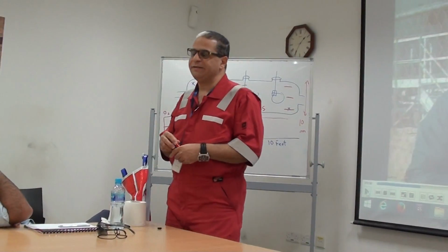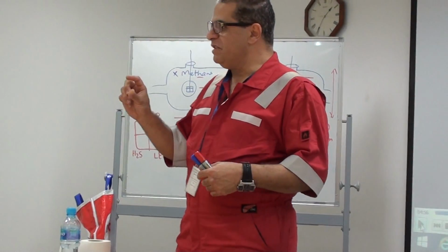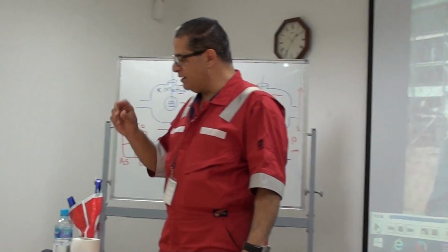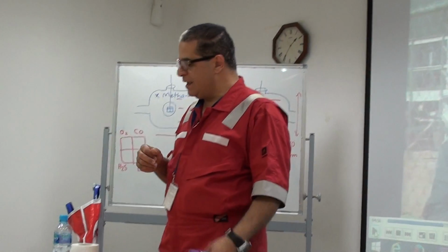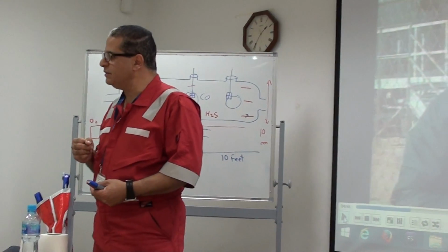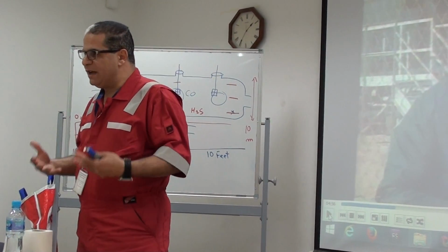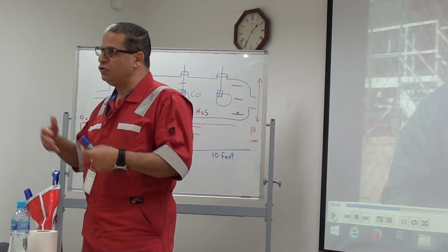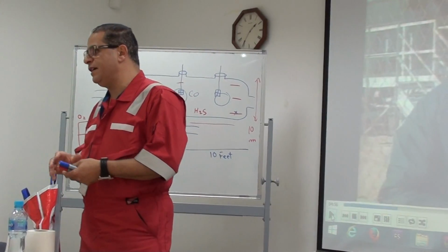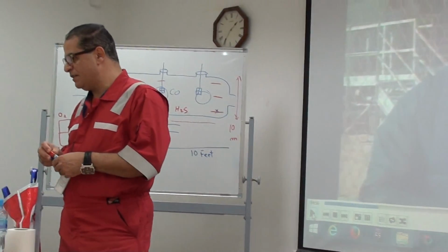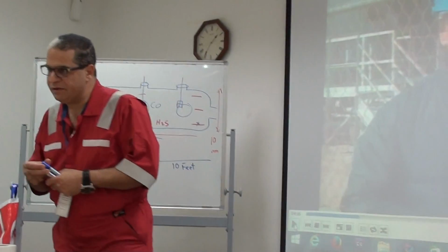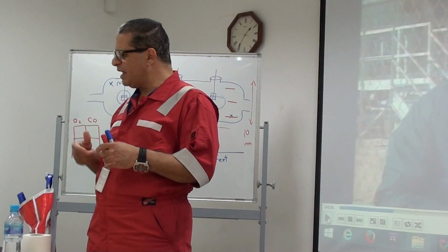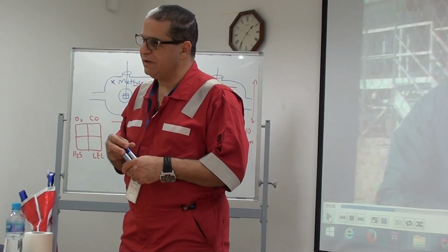How to make sure of that? There are some devices equipped with a strong pump, okay, and the pump does suction of air. When you get the apparatus out in the fresh air, give the apparatus some time to reset itself and to pump fresh air into the tube. This is one method. Another method is to remove the tube, flush it with air, and then insert the tube again.